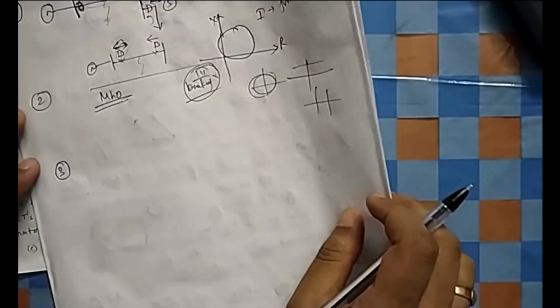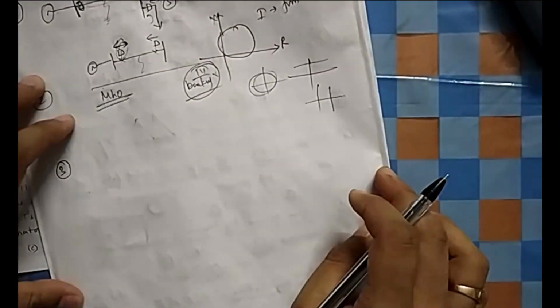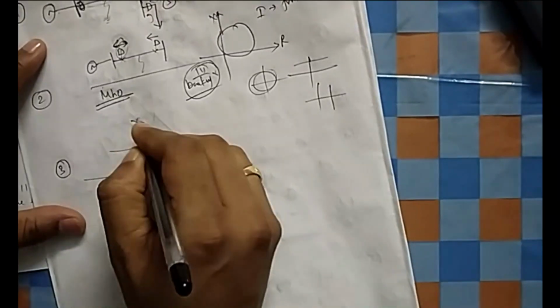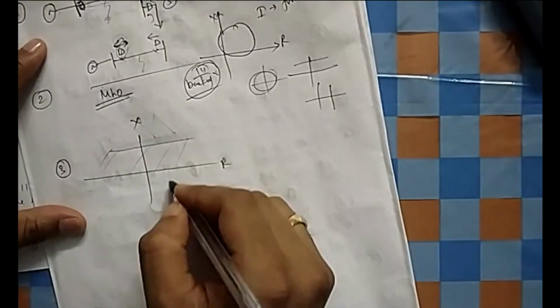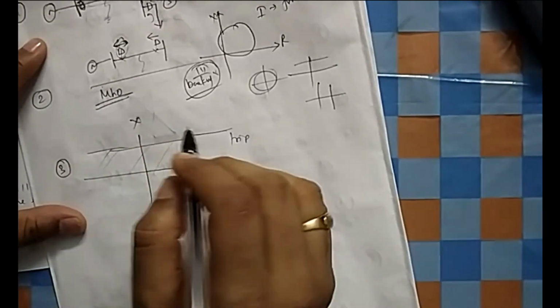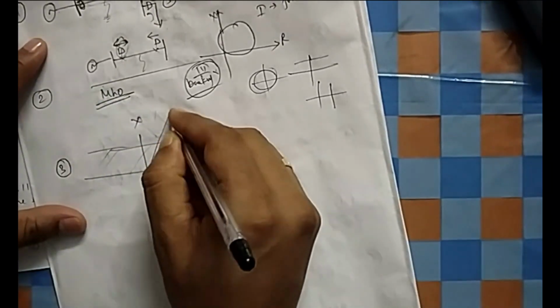The third one is the reactance relay, which is normally preferred for protection against earth faults. If you see the reactance relay characteristics, again you can refer to these trip characteristics. This zone is the trip zone. Below this it will trip. If you set a value below that, it will trip. Now this is the fault characteristic.